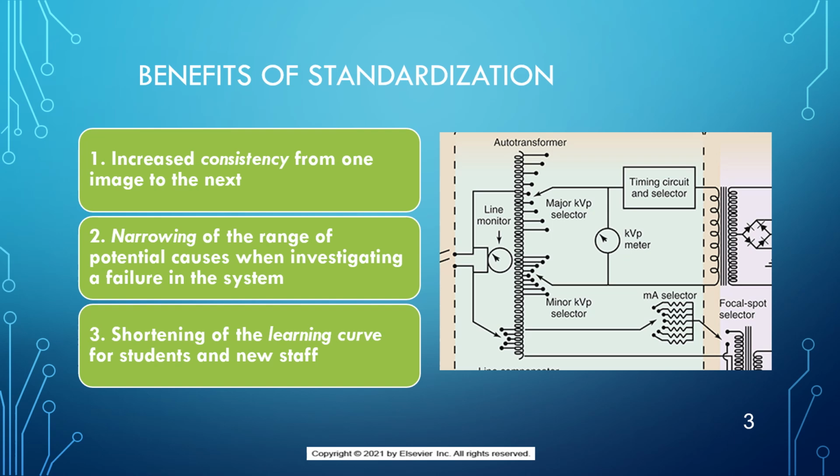Okay, it's harder to figure that out if it's a subtle loss of quality. Now, if it's a radical loss of quality, immediately you know the X-ray system is tore up and it needs repair. Okay, but if it's a subtle loss of quality, if everyone's not using consistent techniques, that subtle loss of quality kind of gets masked in the background and it lingers.